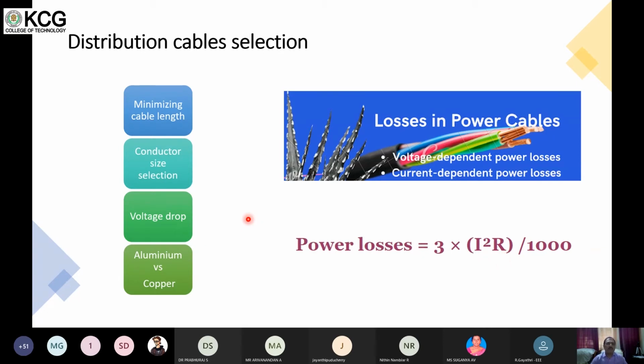So we need to understand how we can address this by minimizing cable length, because as the length increases, the losses increase. Increasing the conductor size. If you recall, I used the term upsize. This is what I meant. Most of the industries do not load their cables for more than 50 to 60% of the total carrying capacity in current. So this is a practice which the industries have, and this is based on the wisdom that conductor sizes have to be higher in order to reduce the resistance and therefore the losses.